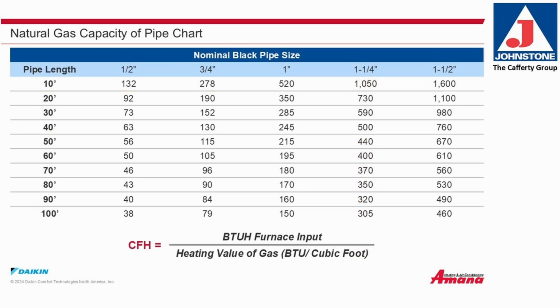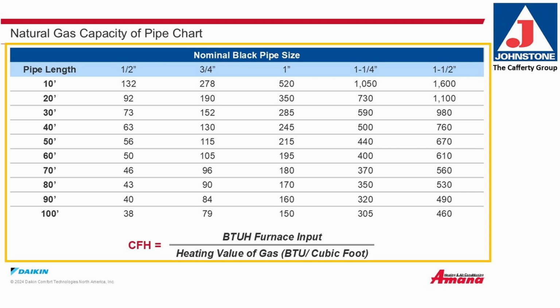Here's an example of a natural gas capacity of pipe chart. This can be found in the installation manual. This chart shows the pipe length, the pipe diameter, and the cubic feet per hour of gas capable of passing through that pipe at that length. To calculate the needed cubic feet per hour, take the BTU input of the furnace over the heat value of the gas in BTUs per cubic foot.